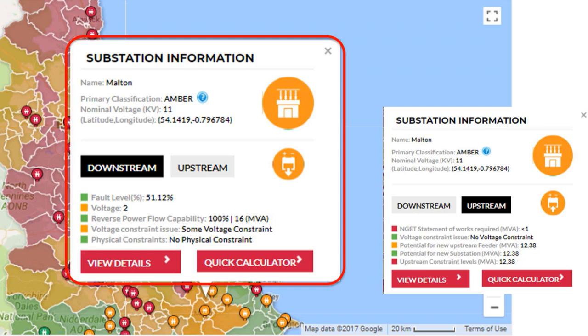The next one tells us about how able we are to move power away from this substation. If the amount of generation within the group exceeded the amount of demand, which can often happen at times of minimum demand, the power needs to flow back up the network to be used elsewhere, and some of our substations are restricted in their capability on this. In this particular case, it's telling us that the capability of the network for power to go in the reverse direction is 100%, so we don't have any issues there, and we give it a green.